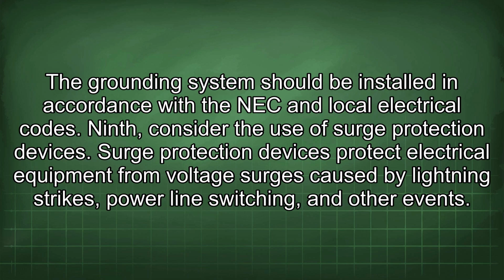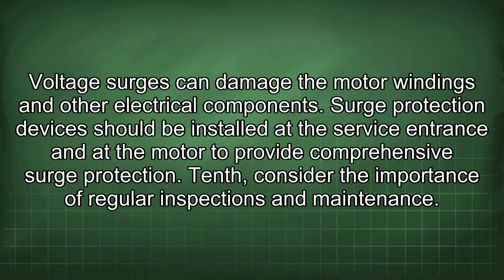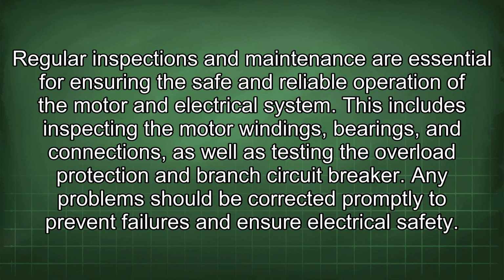The grounding system should be installed in accordance with the NEC and local electrical codes. Ninth, consider the use of surge protection devices. Surge protection devices protect electrical equipment from voltage surges caused by lightning strikes, power line switching, and other events. Voltage surges can damage the motor windings and other electrical components. Surge protection devices should be installed at the service entrance and at the motor to provide comprehensive surge protection. 10th, consider the importance of regular inspections and maintenance. Regular inspections and maintenance are essential for ensuring the safe and reliable operation of the motor and electrical system. This includes inspecting the motor windings, bearings, and connections, as well as testing the overload protection and branch circuit breaker. Any problems should be corrected promptly to prevent failures and ensure electrical safety.